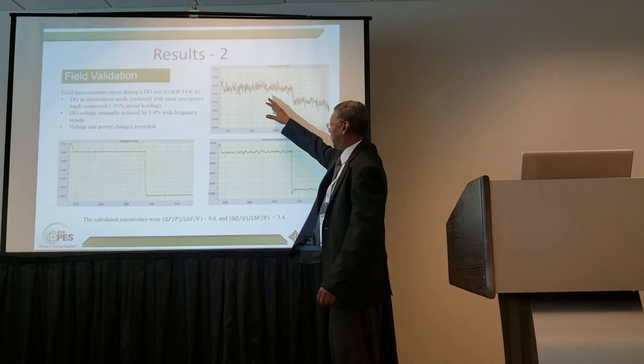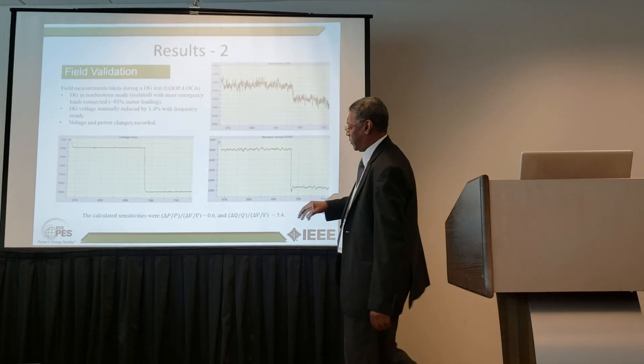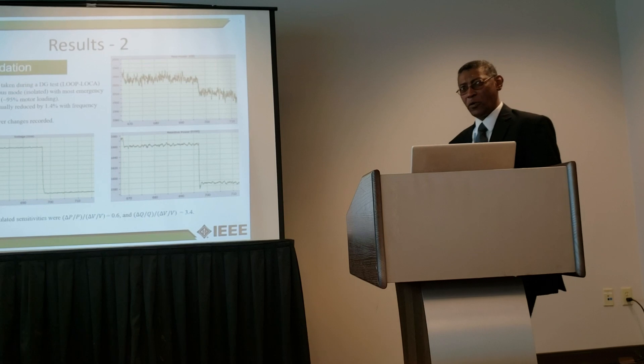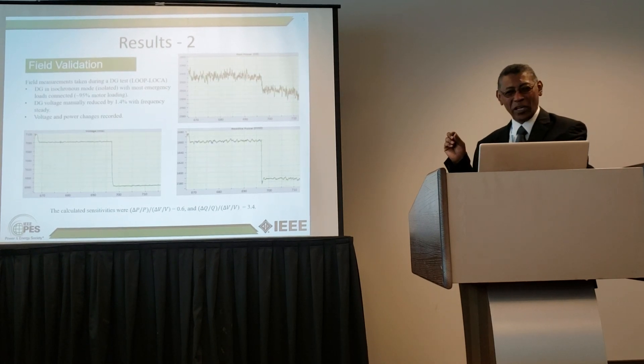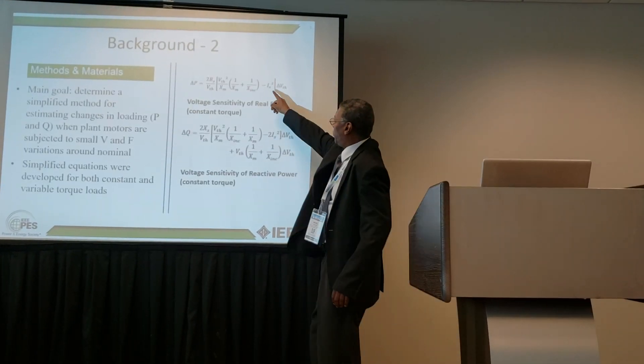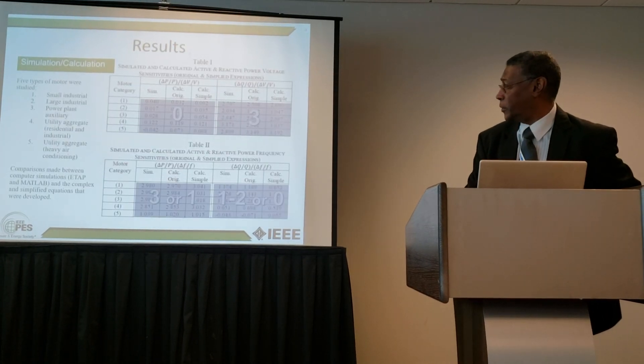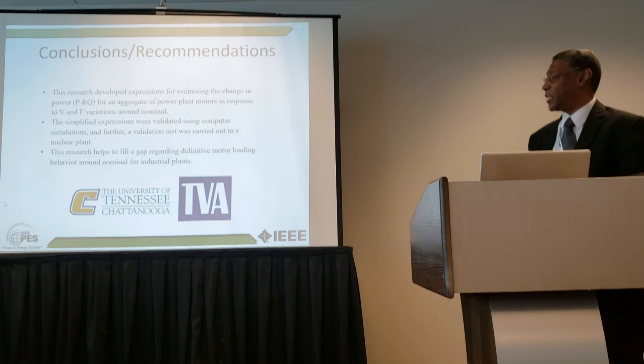It was a voltage reduction test at steady frequency. They looked at active power — active power is quite noisy because it changes little and is hard to measure precisely. We did detect some change in active power with voltage: about 0.6, which is a sensitivity meaning percentage power divided by percentage voltage. Our prediction is around zero plus or minus — there wasn't much surprise here, because when the stator current is small the power change tends to become positive.